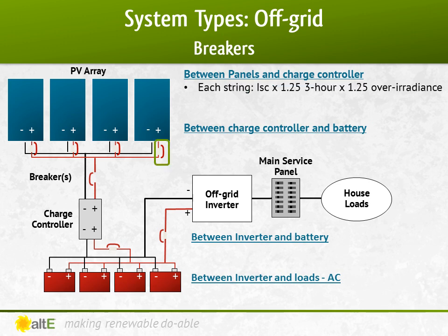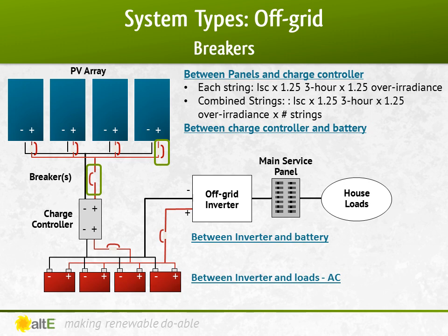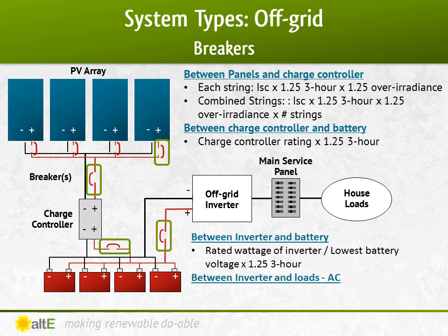Between the panels and the charge controller, each string uses the math of the short circuit current (ISC) times 1.25 for NEC's 3-hour continuous, times 1.25 for over-irradiance. The combined strings use ISC times 1.25 times 1.25 times the number of strings. Between the charge controller and the battery, use the charge controller's rating times 1.25. Between the inverter and the battery, use the rated wattage of the inverter divided by the lowest operating battery voltage, times 1.25. And finally, on the AC side between the inverter and the AC loads, use the rated wattage of the inverter divided by the AC voltage, times 1.25.